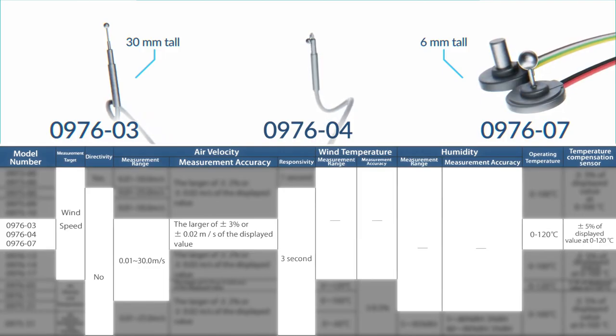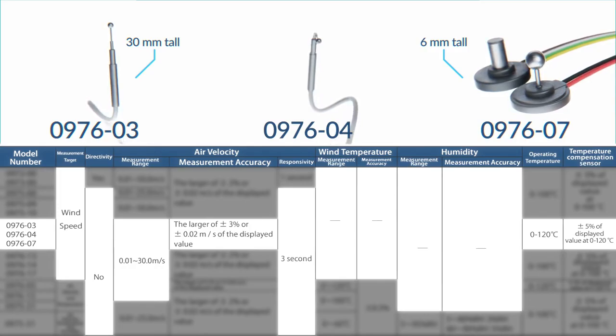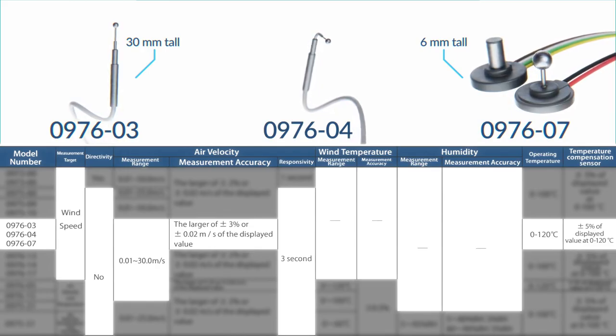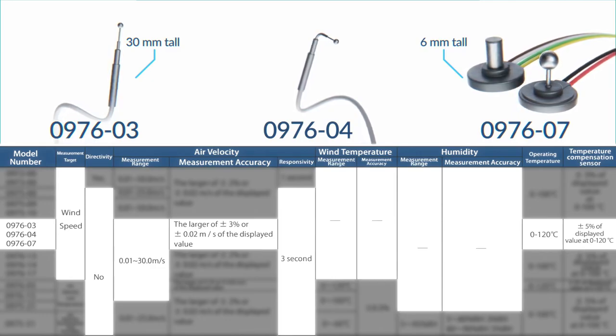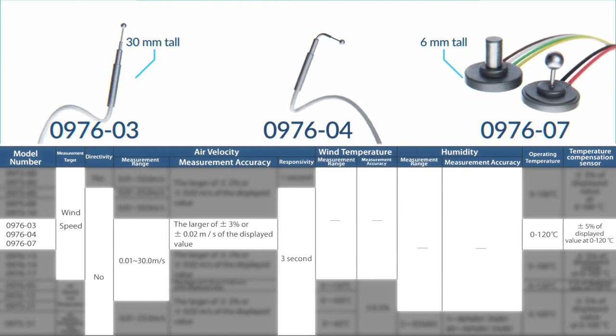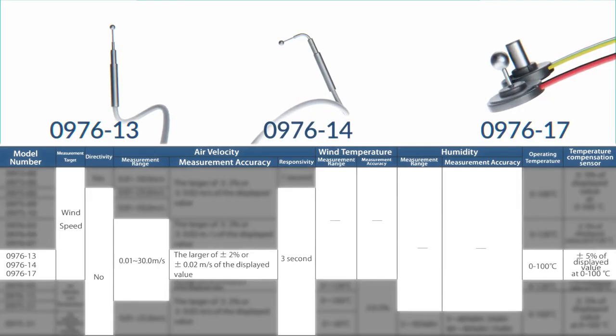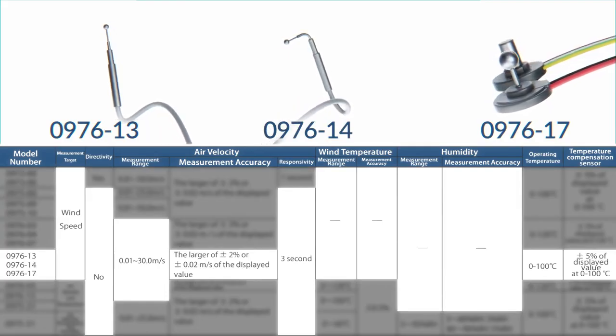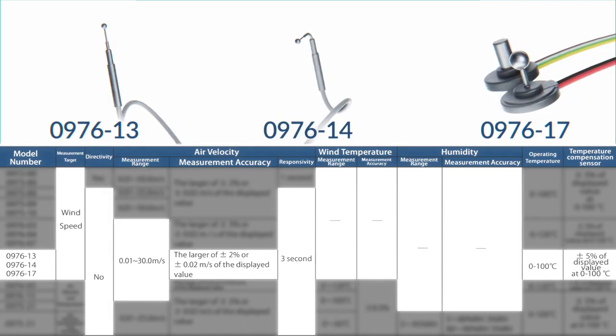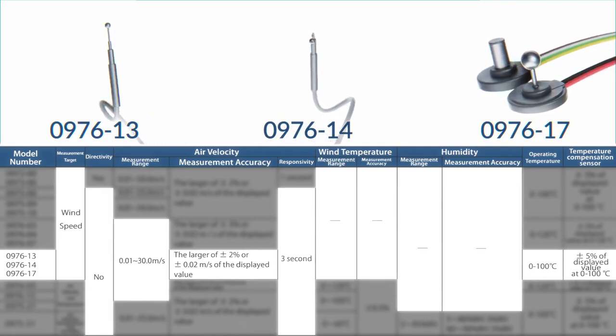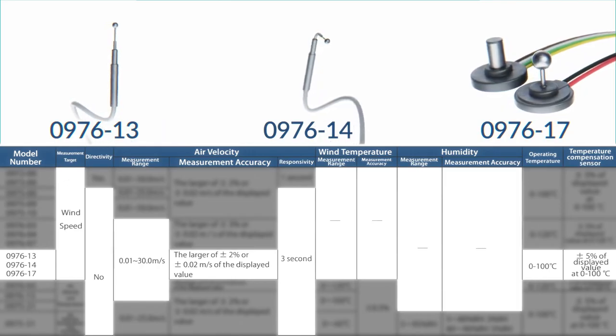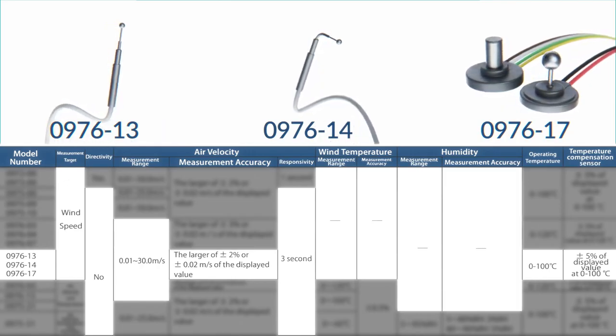0976-03 is a mini straight-type probe, 30 millimeters in length, ideal for doing measurements at moderately high temperatures. 0976-04 is also a miniature-sized probe, but features an articulated neck for those hard-to-reach areas. 0976-07 is a new microprobe that's just 6 millimeters tall, perfect for microelectronics and PCB cooling efficiency testing. Models 0976-13, -14, and -17 are almost identical to 0976-03, -04 and -07, but are not as heat resistant, operating at temperatures from 0 to 100 degrees Celsius, and feature improved measurement accuracy.